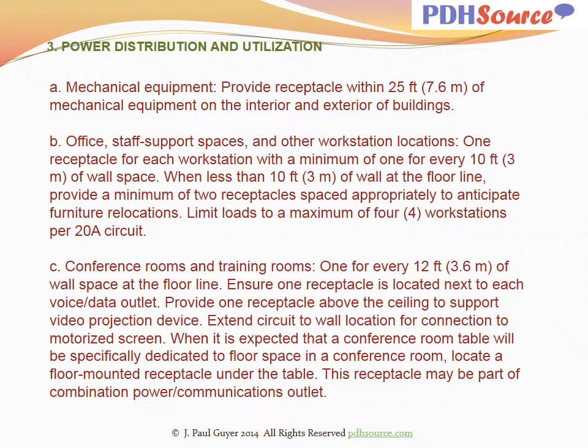Office, staff support spaces, and other workstation locations, one receptacle for each workstation with a minimum of one for every 10 feet of wall space. When less than 10 feet of wall at the floor line, provide a minimum of two receptacles spaced appropriately to anticipate furniture relocations. Limit loads to a maximum of four workstations per 20 amp circuit. For conference rooms and training rooms, one for every 12 feet of wall space at the floor line.